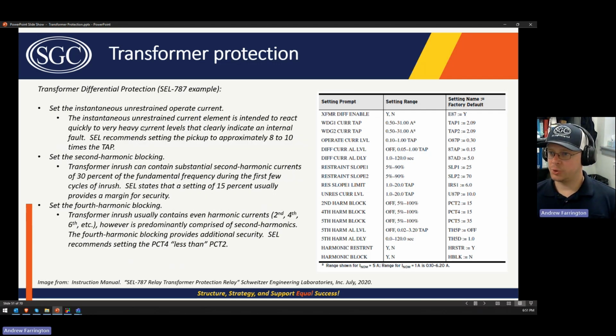Okay, the unrestrained differential element we talked about. It's usually like 8 to 10 times the tap setting. So these are currents that are high enough that you're not going to be operating on the slope characteristic, and you know that the fault is internal because you can't achieve those differential currents for an external fault. Just go ahead and trip.